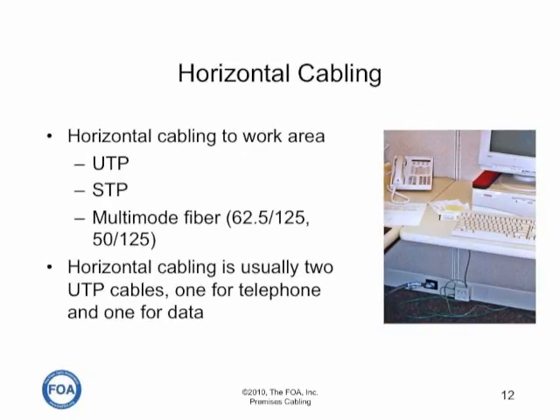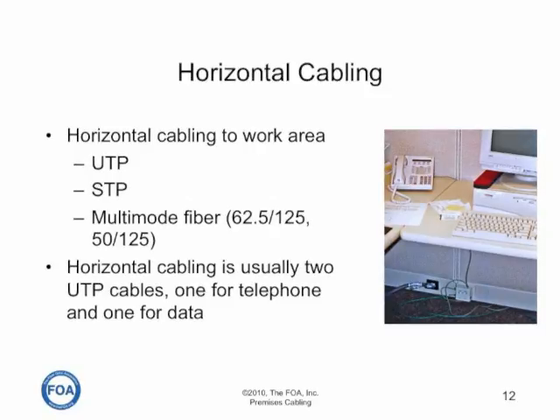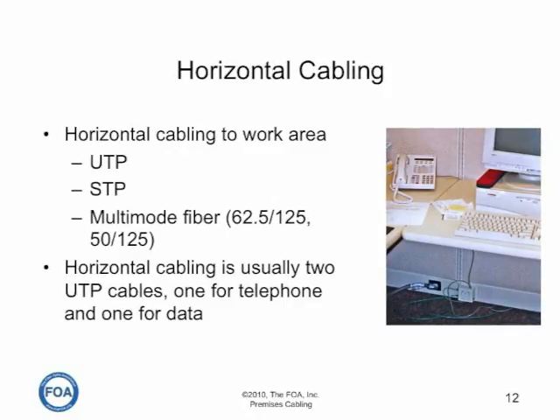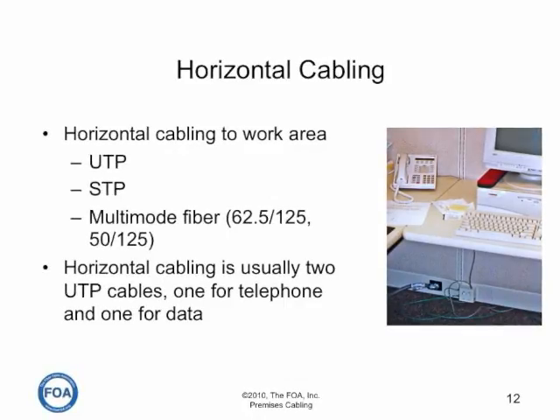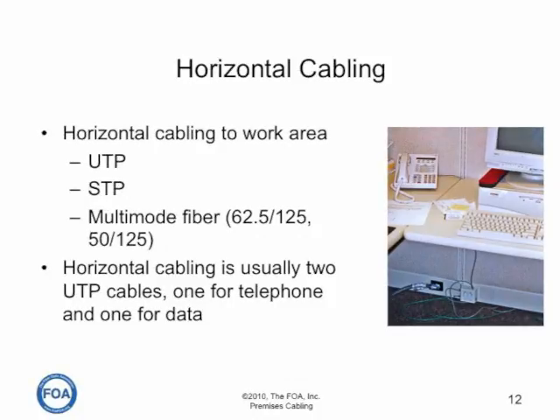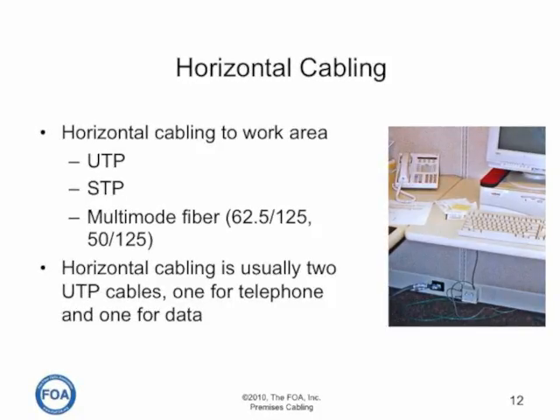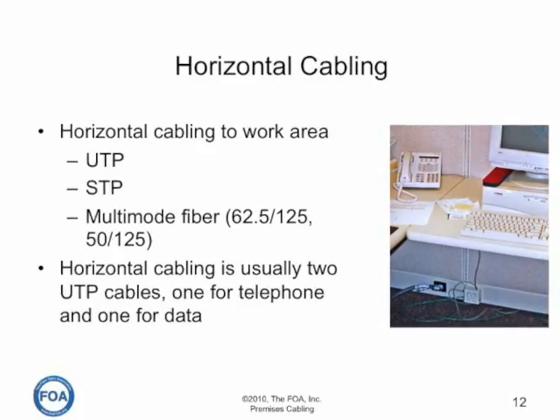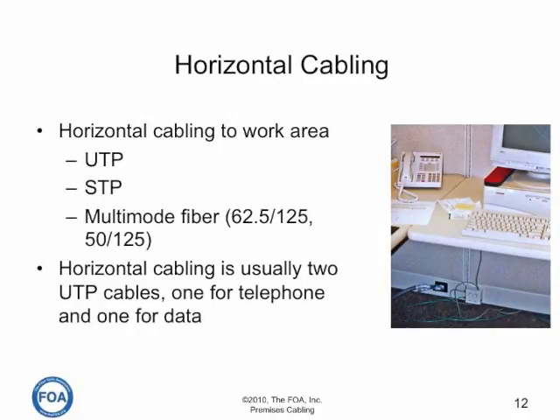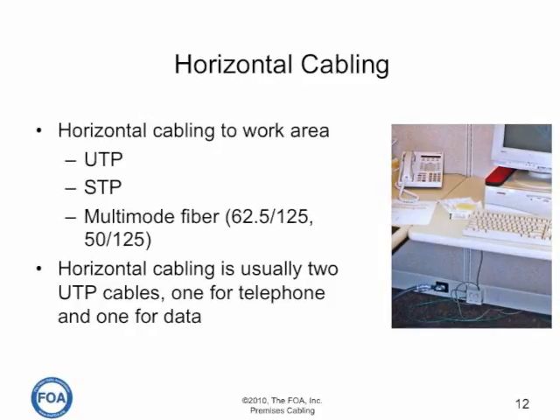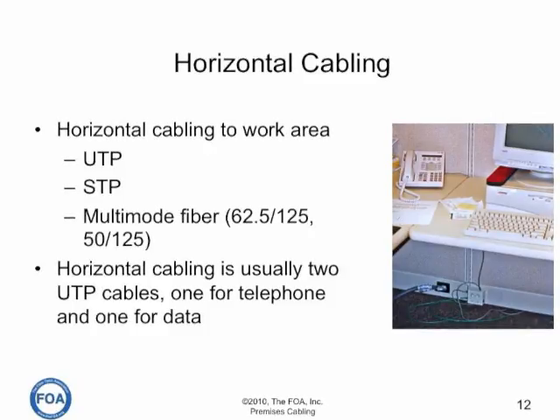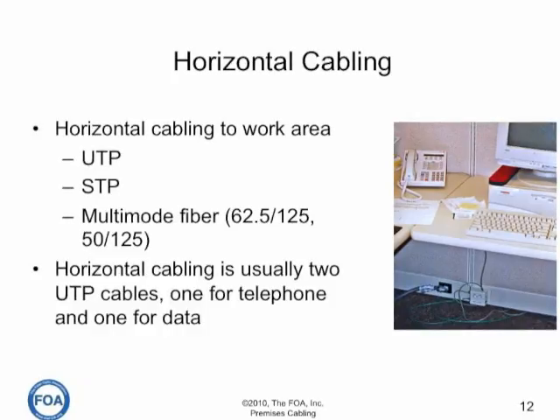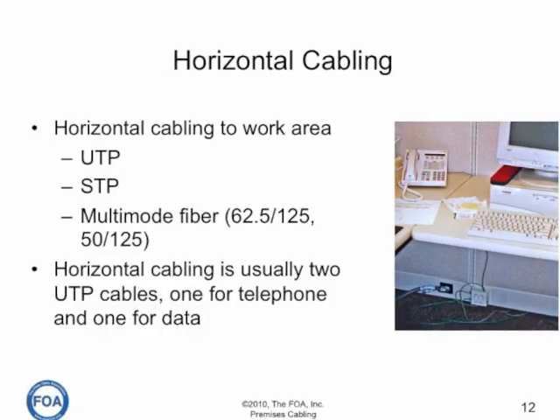Horizontal cabling is the cabling that connects the work area to the telecom closet, or in today's network, it also connects wireless access points back to the telecom closet. It can be UTP, or shielded or screened twisted pair, or multi-mode fiber. Although today it's usually unshielded twisted pair cables — one for telephone and at least one for data. With the advent of wireless networks, less and less workstations or work areas are being cabled with copper connections; more and more are simply relying on the wireless networks in the building.